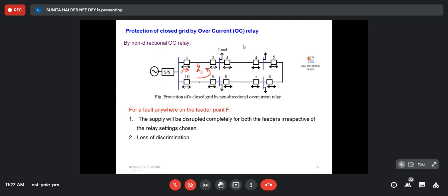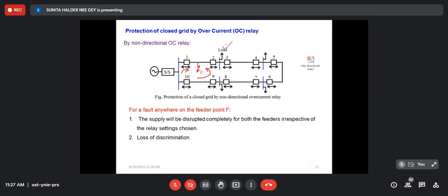If fault is in section 1-2, we expect only relays 1 and 2 to disconnect. Relay 3 cannot identify that it has no need to operate, so it will operate, and the load connected to that bus will get disconnected unnecessarily. That is not expected — one protection system should not cause that. That's why a directional overcurrent relay is required.